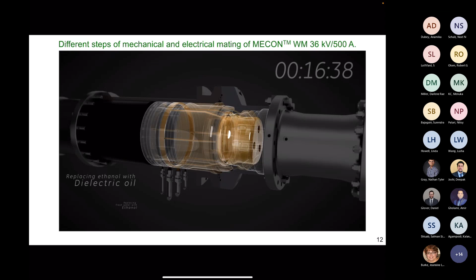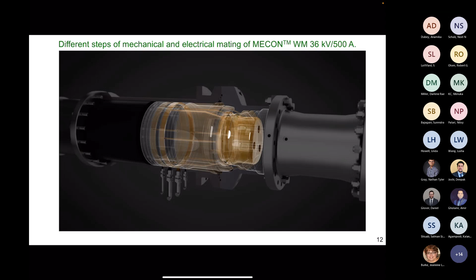And after this, you eventually need to fill the chamber with dielectric oil, which is the electrical insulation in this system. So the whole purpose of this project was choosing the proper dimensions and materials for the insulation system, in a way that my criterion was not wanting to see any streamers in the liquid dielectric under both normal conditions and especially under transient conditions, transient overvoltages.